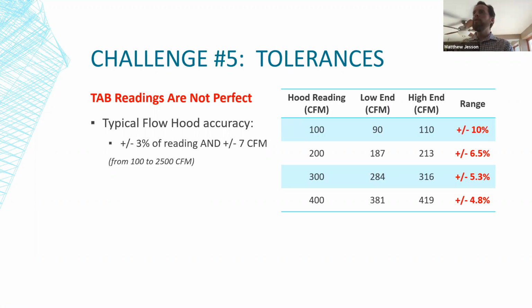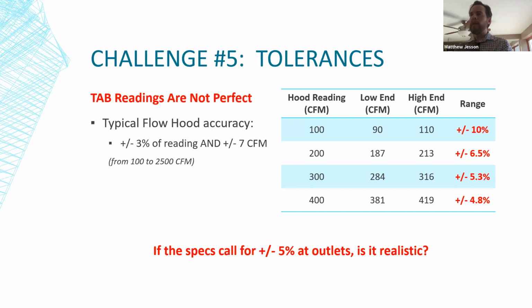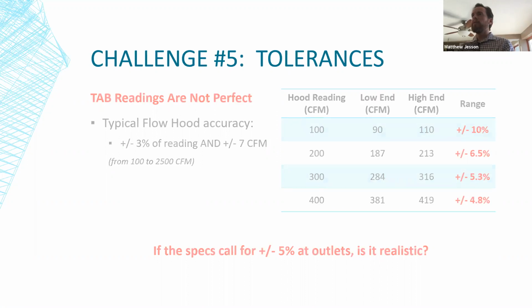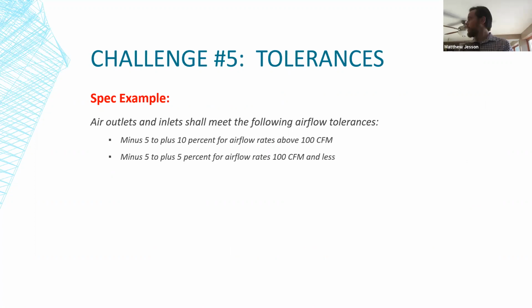So if we do the numbers on that, at a hood reading of 100 CFM, the range of that is really plus or minus 10%, just as far as the hood accuracy is concerned. And as you go up in airflow, that range gets a little tighter. By the time you get to 400 CFM, it's under 5%. But still, most scientific measurements are tighter than your airflows. So if the specifications call for plus or minus 5% at the outlets, is it realistic? So I'm going to go into a few examples that are directly out of specifications that I've worked on.